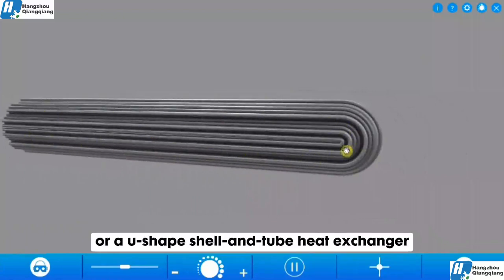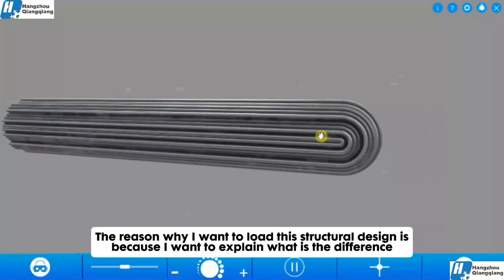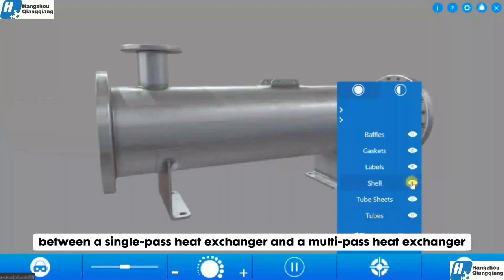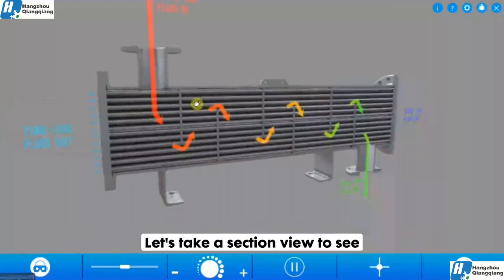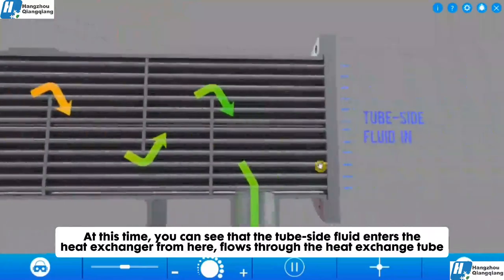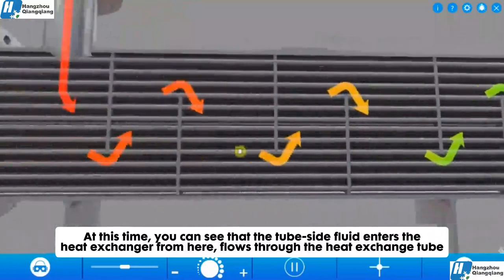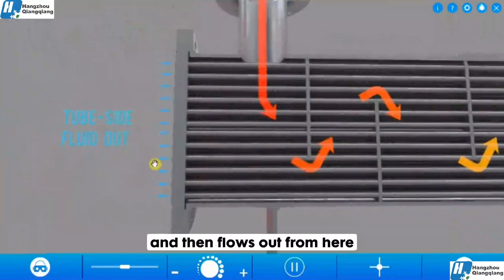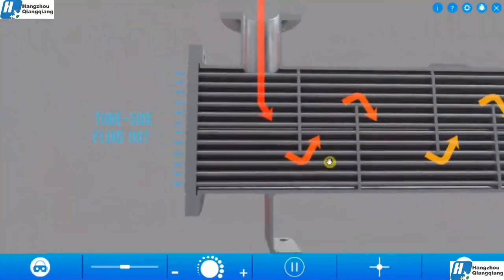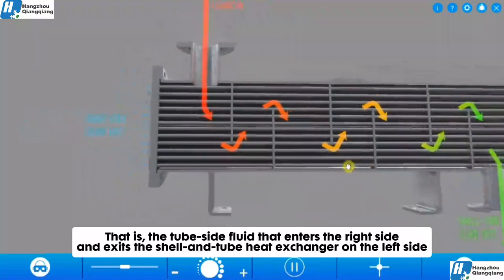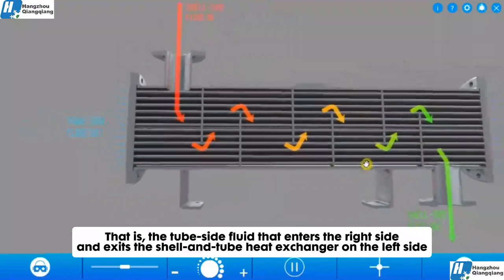The reason why I want to load this structural design is because I want to explain the difference between a single-pass heat exchanger and a multi-pass heat exchanger. Let's take a section view to see. You can see that the tube side fluid enters the heat exchanger from here, flows through the heat exchange tube, and then flows out from here — entering on the right side and exiting on the left side of the shell and tube heat exchanger.